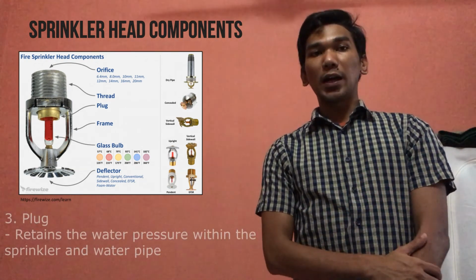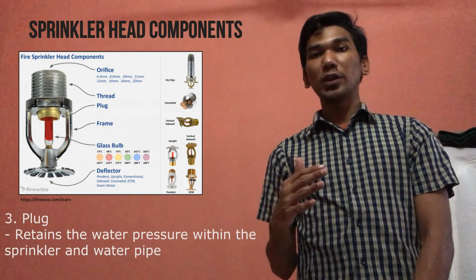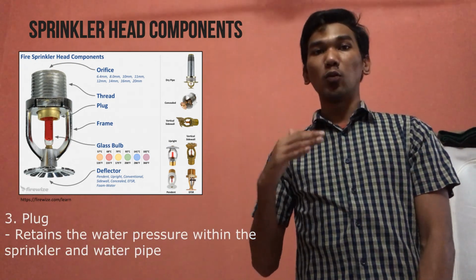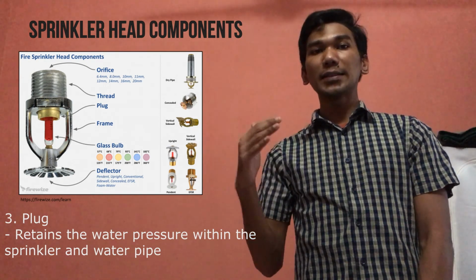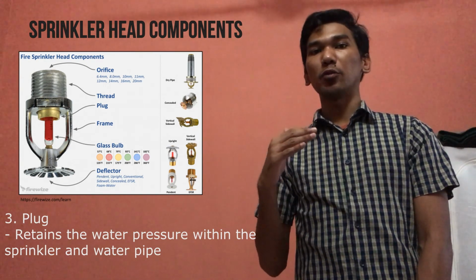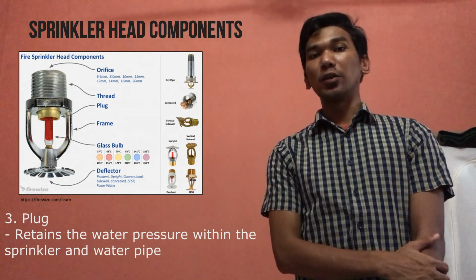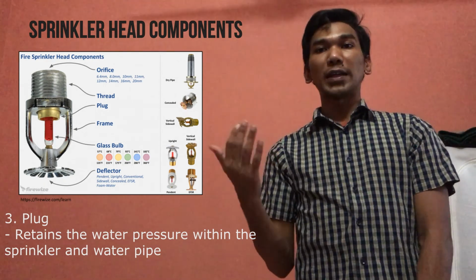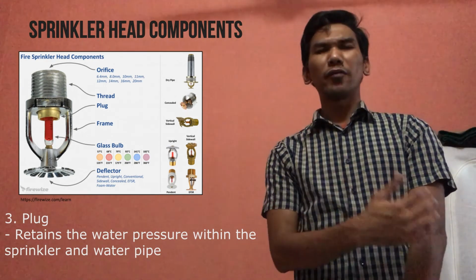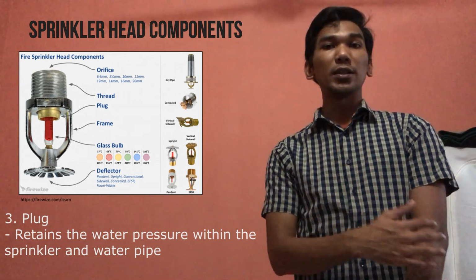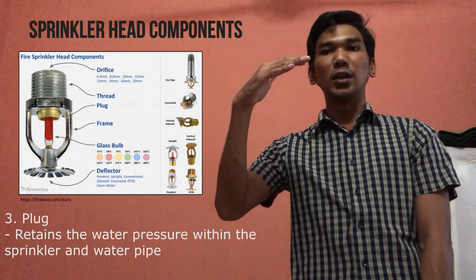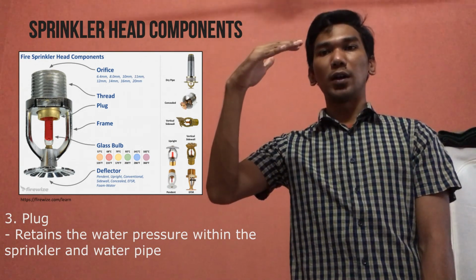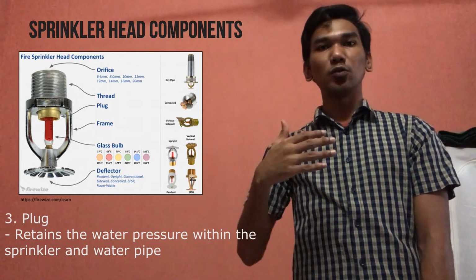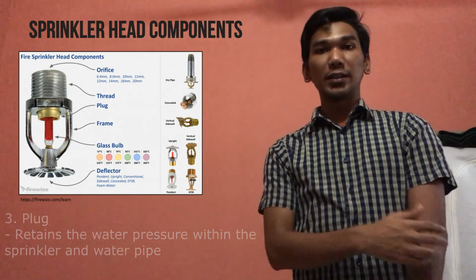The third one is the plug. It retains the water pressure within the sprinkler and the water pipe. So when the glass bulb is broken, the plug will release the water from the pipe and send it to the deflector. We can see that the function of the plug is very important because it holds the water pressure from breaking through the sprinkler itself.